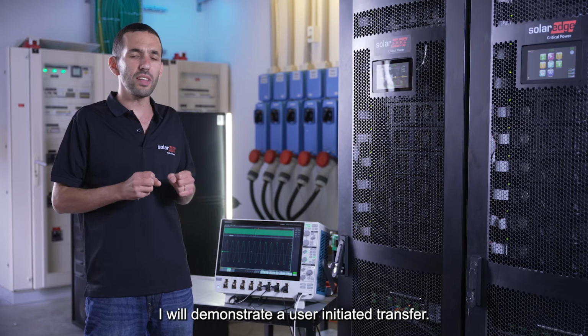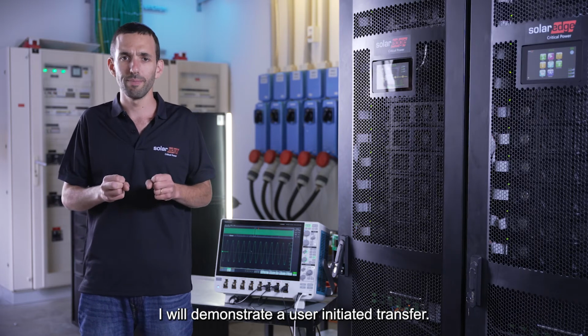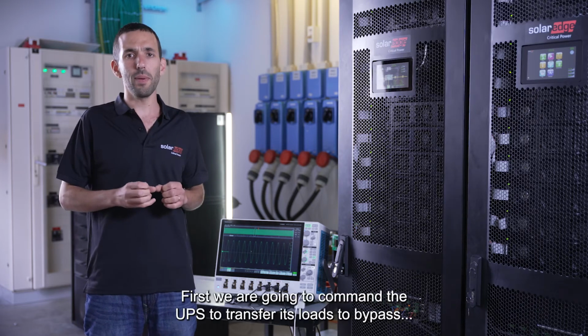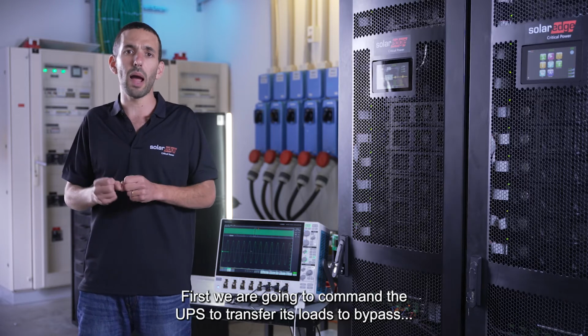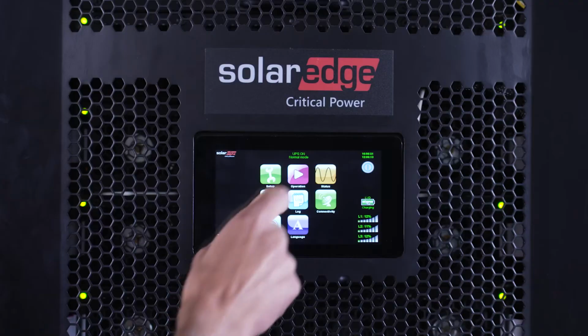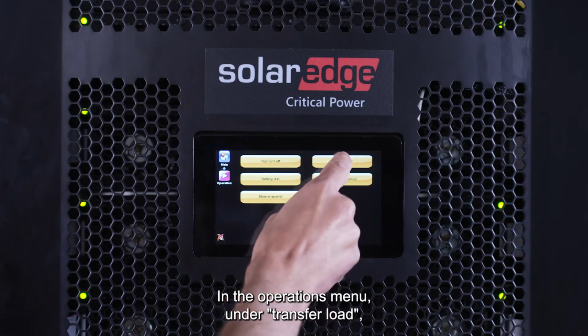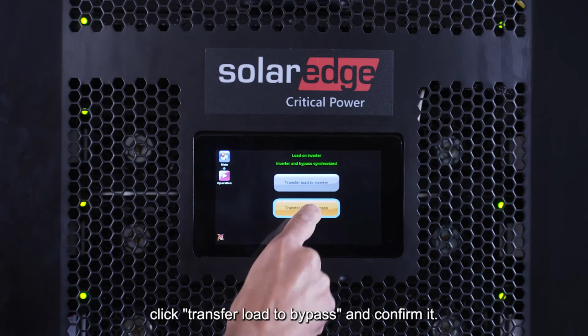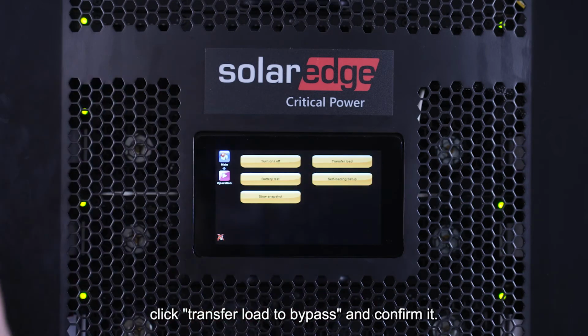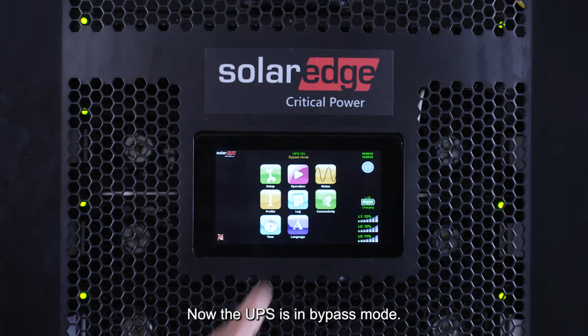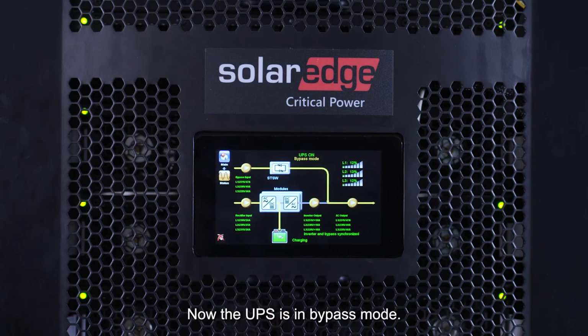I'll demonstrate a user-initiated transfer. First, we're going to command the UPS to transfer its loads to bypass. In the Operations menu, under Transfer Load, click Transfer Load to Bypass and confirm it. Now the UPS is in bypass mode.